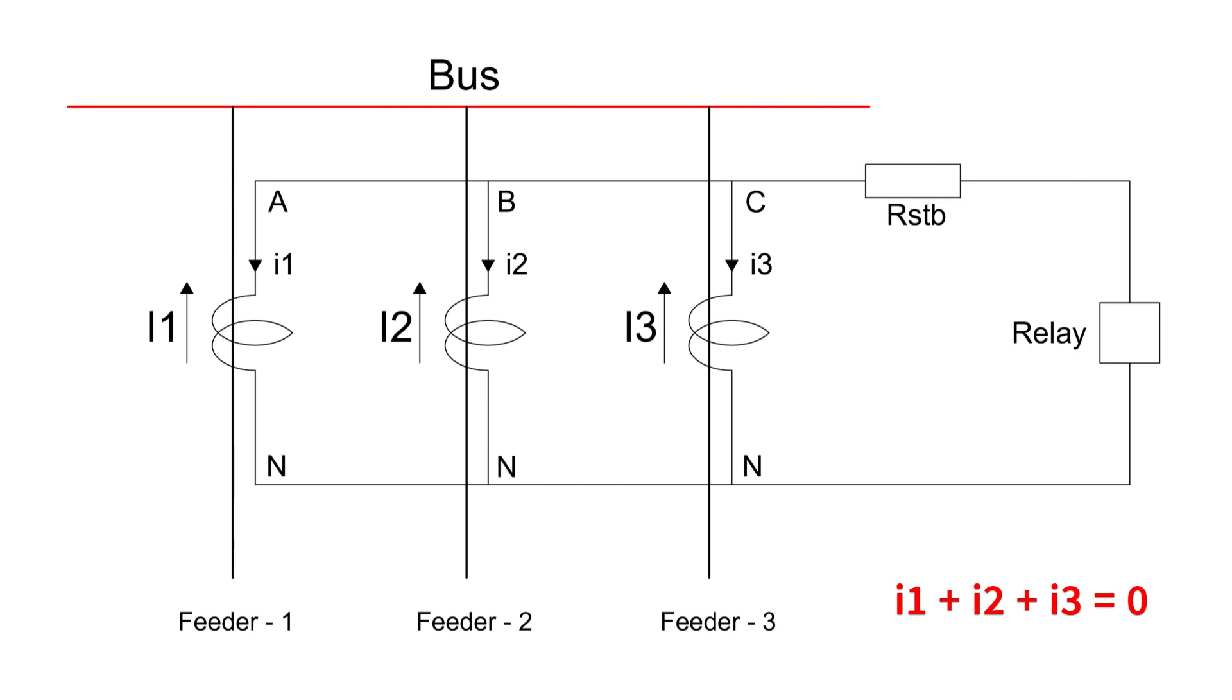Mathematically, under normal conditions, I1 plus I2 plus I3 will be zero. Since the relay sees only the summation of current, we typically employ an overcurrent element in high impedance differential protection. This is the key difference between high impedance and low impedance differential protection.